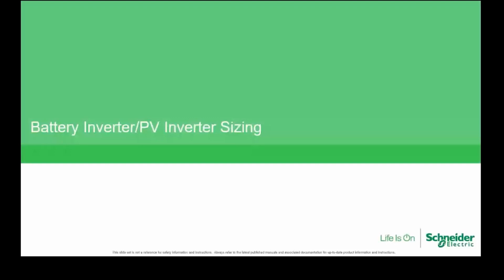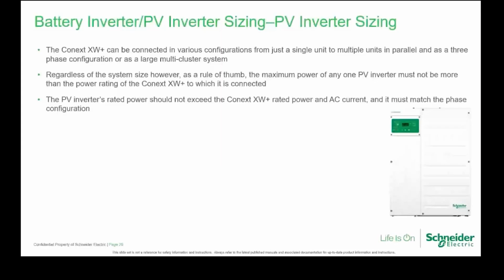Okay, battery inverter and PV inverter sizing. You can use various configurations from a single unit to multiple units in parallel, or as a three-phase configuration, or as a large multi-cluster system. Regardless of the size, however, we use a rule of thumb. Basically, the maximum power of one PV inverter must not be more than the power rating of the XW Plus or XW Pro to which it's connected. So the PV inverter's rated power should not exceed the XW Plus rated power and AC current, and it must match the phase configuration.